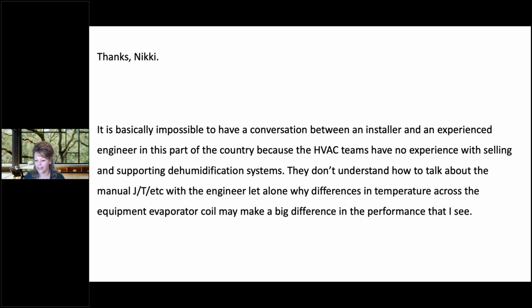We've seen a huge adoption of our equipment over the last 10 years, there's no doubt, but there's still a lot of installers that believe the AC can handle it 24/7, 365 days of the year, depending on where you live and what your latent loads are. So it was a very eye-opening conversation, because I feel like we've made such large leaps in getting dehumidification adopted, but there's still a long way to go. And we are going to be in a tough situation the tighter our houses get, and with the pushback we get from the industry on actually utilizing dedicated dehumidification systems.